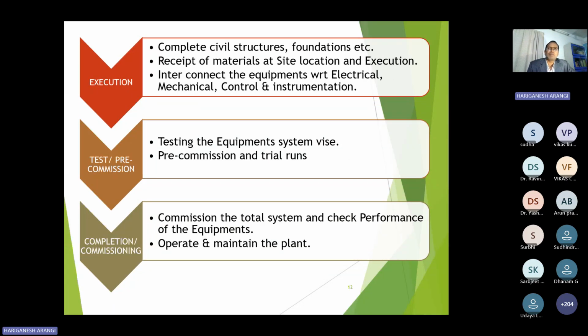Then after that, material will be supplied to the land where you have proposed and taken the approval. There, execution will take place with respect to the civil, mechanical, electrical, and instrumentation. Then the total execution work will be completed, and even before running any equipment, motors will first be taken for no-load trials, without coupling, to check whether the installed motors and installed cables are okay or not. Those tests will be done. That is called pre-commissioning checks.